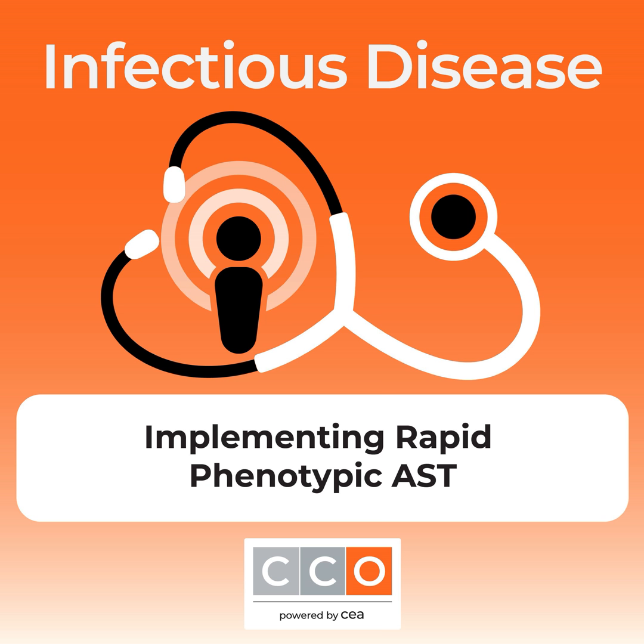It's not that the instrument has any technical limitation, it's that there is a limitation in regard to the indication for that particular drug. There could be another gap, a drug-bug mismatch where there is an indication and the instrument doesn't give you that information, because there could be some limitation of the performance. So in those two different aspects, it's important to discuss with the manufacturer when you decide what platform fits for you. Does that answer your question?